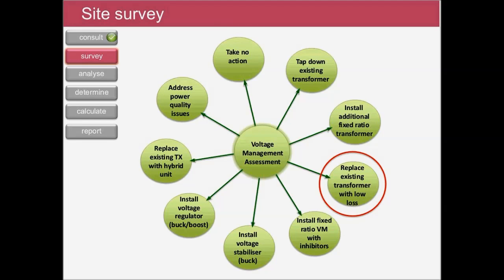In another application, the best practice may be to replace the existing transformer with a modern equivalent to reduce losses or to provide an extended tapping range to facilitate voltage reduction and voltage management at the same time. Where viable and where more erratic voltage profiles are evident, then regulators capable of bucking and boosting the voltage can be used to provide a steady, predetermined output, although the reaction times of this kind of technology should always be checked against the characteristics of the supply and any voltage-sensitive equipment on site.